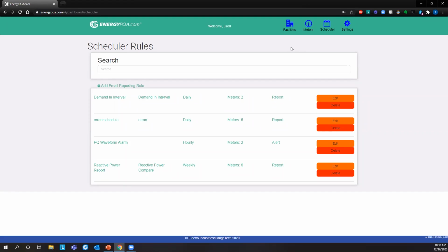Again, at the very beginning, when you start using Energy PQA and you don't have a whole lot of historical information, you might start getting quite a few emails for updates as the machine learning and artificial intelligence calibrate to your system. But once you have quite a few months or a year of information, both usage and weather, Energy PQA starts dialing in, and you won't get emails every day. You'll only get emails as a significant event changes the predictive demand. But now again, you can have an email saying, this month, I expect your demand to be this high on this day. So now you have a little more time to start figuring out how you're going to adjust that day to minimize your demand.